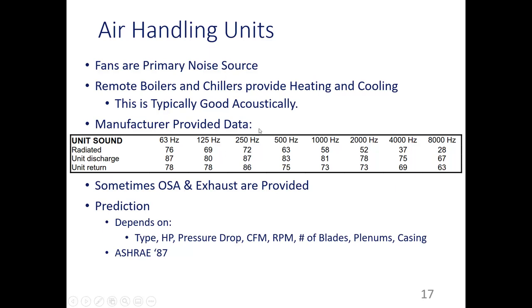Or if applicable is better. Better way of saying that. And say you had all this data, and then you also had outside air and exhaust here. If you were doing an environmental thing, it might depend on how it's oriented, like if something is really exposed to the outside air or just the exhaust, but it's not just going to be the radiated that radiates out from it. In that case, unless there's some ductwork on it and silencers and stuff like that, then you're just going to want to use the outside air and the exhaust and the radiated. That would be the most conservative thing, is sum those three up and then calculate what the sound pressure level will be at a distance from that unit.